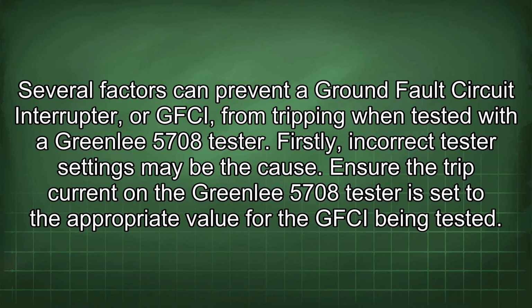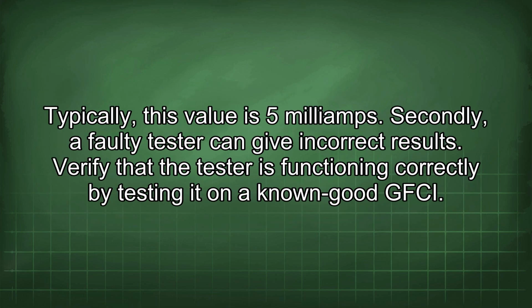Several factors can prevent a ground fault circuit interrupter, or GFCI, from tripping when tested with the Greenlee 5708 tester. Firstly, incorrect tester settings may be the cause. Ensure the trip current on the Greenlee 5708 tester is set to the appropriate value for the GFCI being tested. Typically, this value is 5 mA.